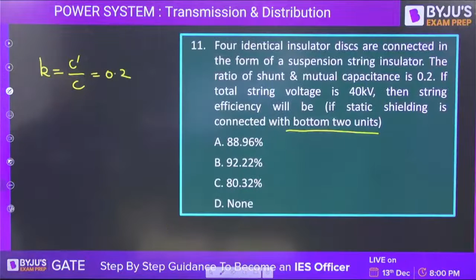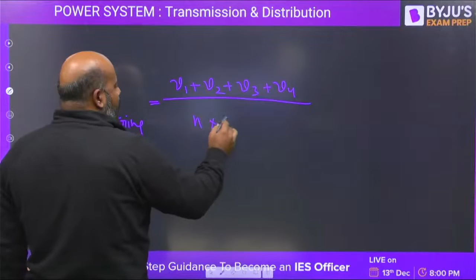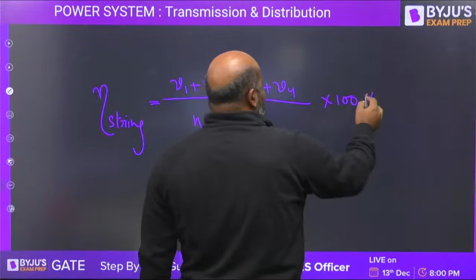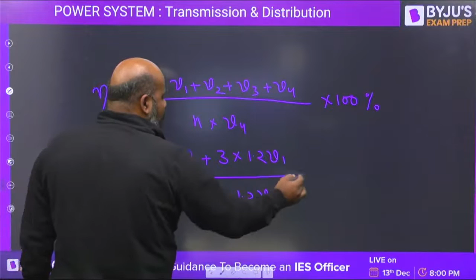He is asking what is the string efficiency. How are you writing the string efficiency? The string efficiency is V1 plus V2 plus V3 plus V4, divided by the number of units and the voltage across the unit nearest to the conductor, that is V4, multiplied by 100%. V1 is V1. Now V2, V3, V4 are same, so 3 times. What is V2? 1.2 V1, divided by N which is 4. What is V4? It is nothing but V2. So 1.2 V1 multiplied by 100. Just solve it. You will be getting your answer.